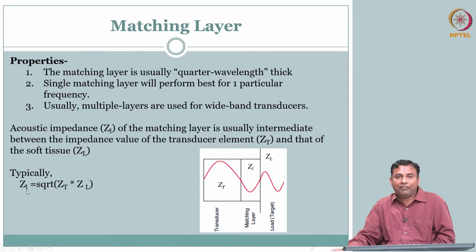So you can get your Z effective to be the square root of your transducer impedance and tissue impedance. Okay. So again, these are engineering the matching layer, which we will go a little light on. We will assume that okay, there is a material science, you have to adjust the impedances, and so materials manufacturing has a lot of role in this part of the instrumentation.